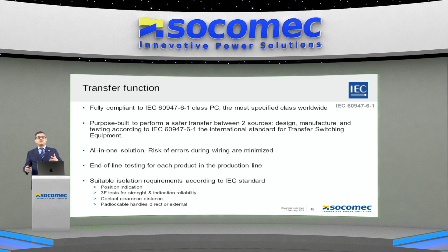Suitable isolation requirements according to IEC standards give an idea of what details are incorporated. It's not just a standard to read from; there are conditions which need to be complied with, requiring a lot of back-end planning. This includes the position indicator, 3F test for strength and indication reliability, contact clearance distance, and padlocking handles, both direct and external.